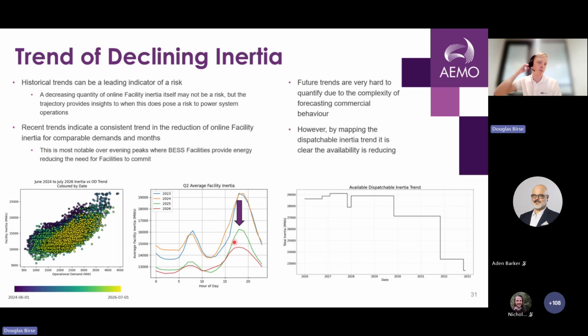What we believe that's because of is battery facilities shifting energy from the middle of the day to the evening, such that you don't need to commit as many units in the evening to provide inertia. That change is rapid — within 3 years, a reduction of 25% of the facility inertia is really quite a drastic shift in the power system we're operating with.